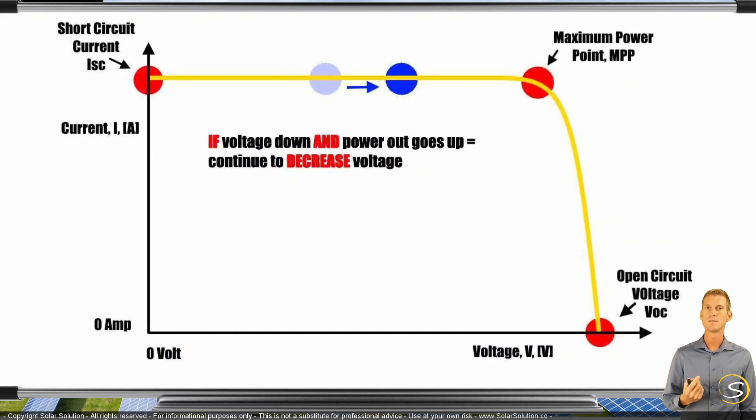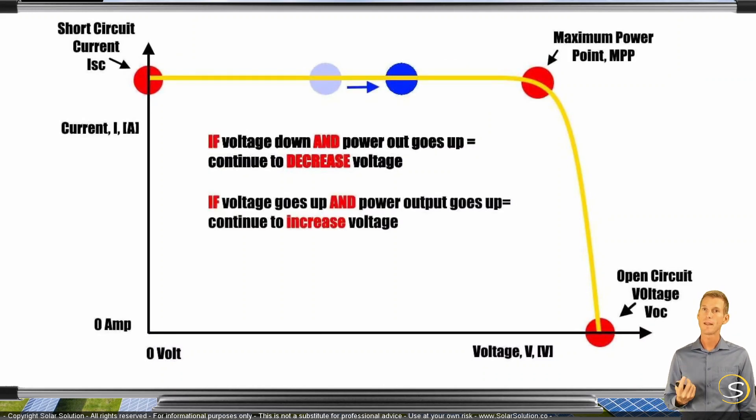So then it follows the second set of rules whereby it says, well, if I would increase the voltage, if the voltage goes up and the power output goes up, it will continue to increase the voltage. And this is the core essence. This is the core operating principle of an MPPT solar charge controller.